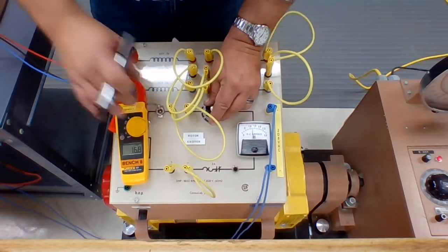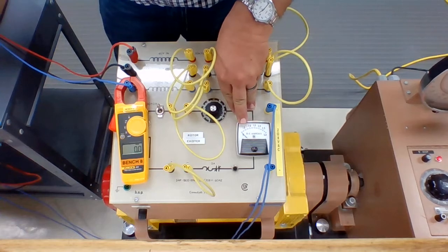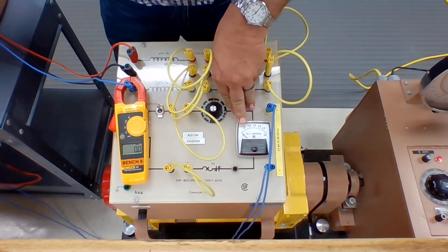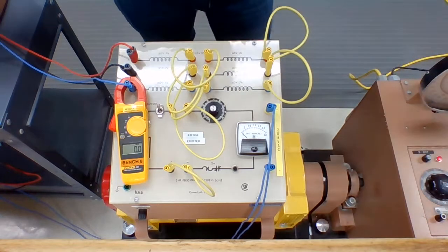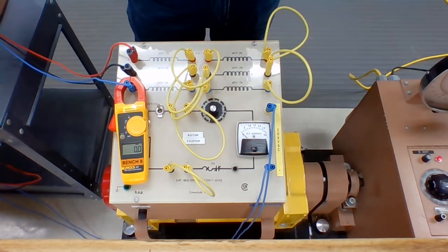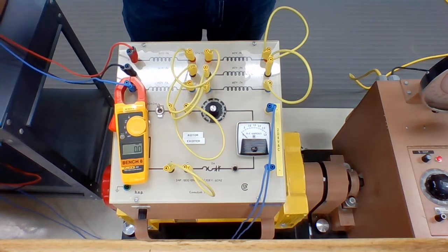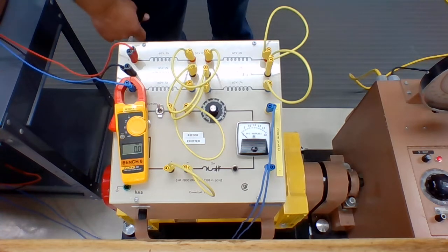Oh, and now you'll see our currents are jumping all over the place. When I went down to 0.5 amps of field current, there wasn't enough magnetic field being produced on that rotor to maintain that magnetic link. So that motor actually dropped out of synchronization, and our currents went up, and it bounced around. It was doing terrible things. So we needed more than half an amp of field current to maintain synchronization.